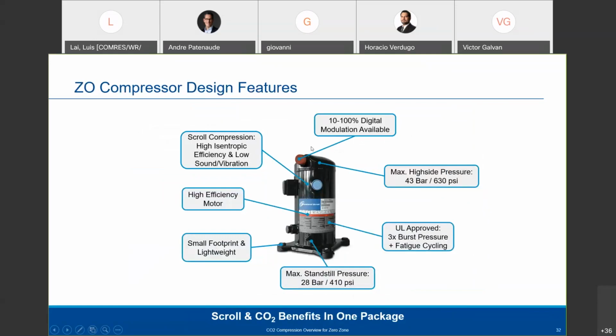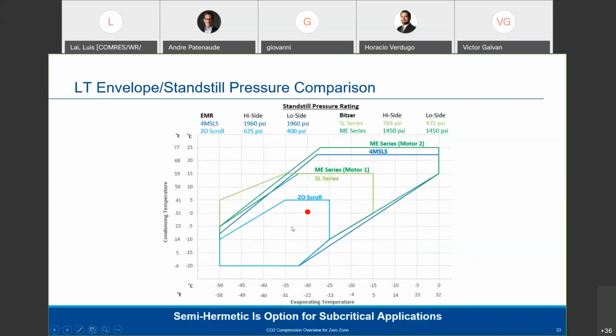So we know it's digital. Don't have to explain too much about that capacity modulation. What's interesting, the high side maximum pressure is 43 bar because that top shell is thicker than the rest of the body, and can handle higher pressures. And then the maximum standstill pressure for the suction shell is about 28 bar. You got an oil fill and drain, sight glass, and obviously it's a small footprint, and it has the reliability of our scroll.